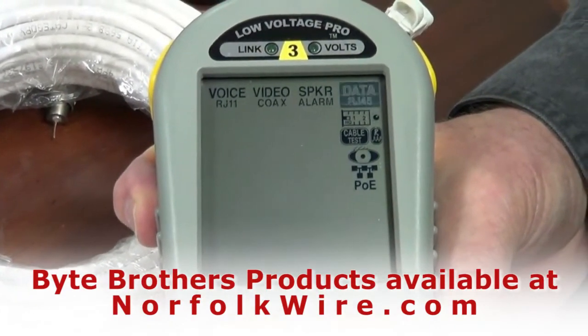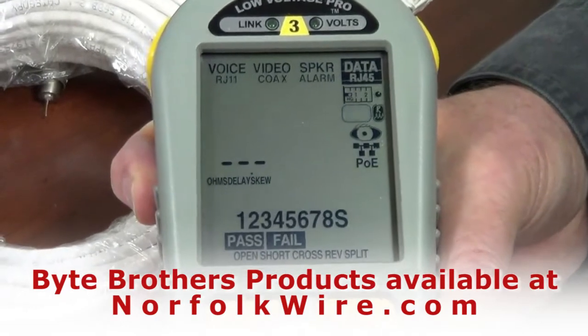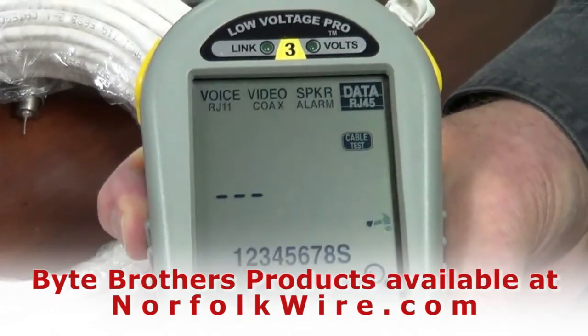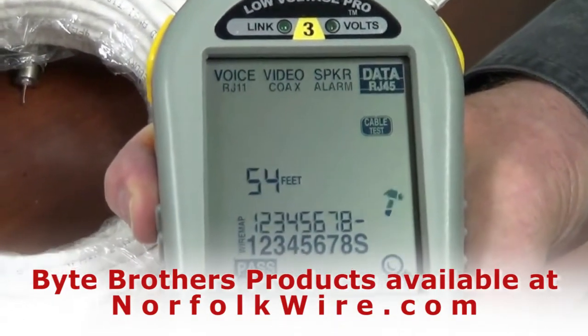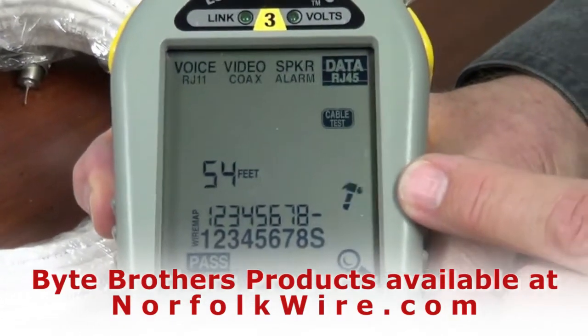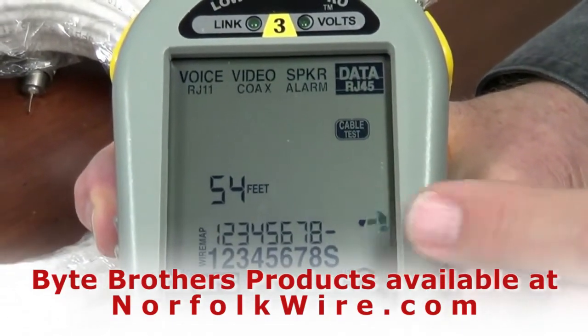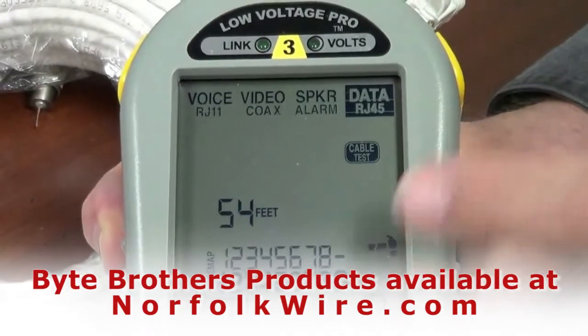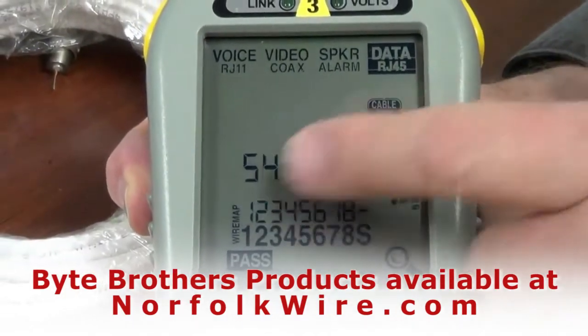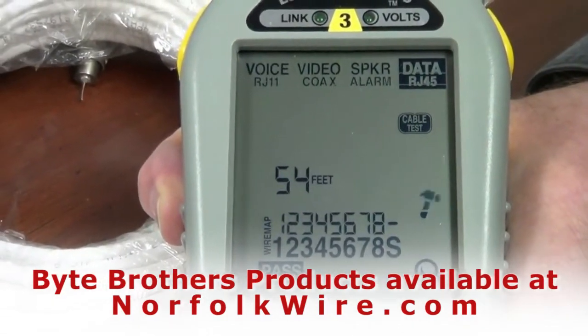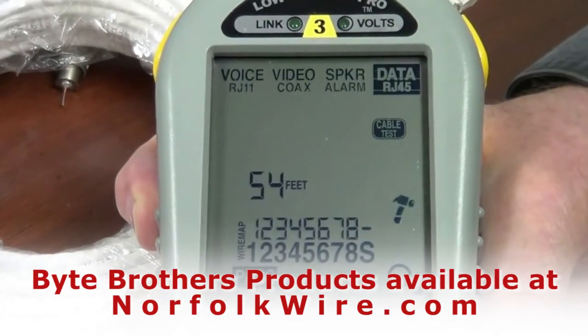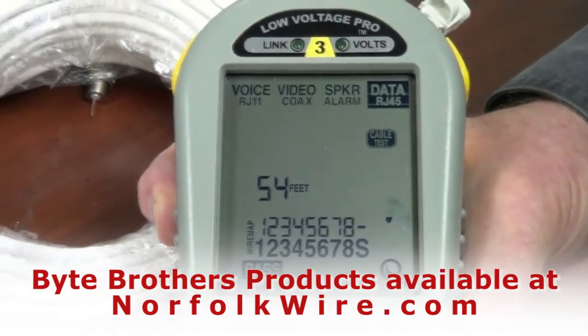So we're on a data cable. We go down to the cable test and press OK to start all of the Low Voltage Pro tests. The hammer starts moving, meaning the tester is running, and it shows me that I've passed, and that's my wire map. The cable is 54 feet long because this particular tester has the length app installed. But look what else you get.